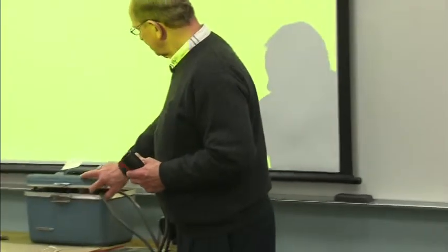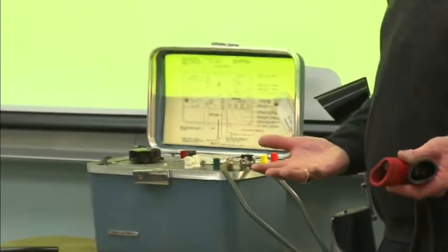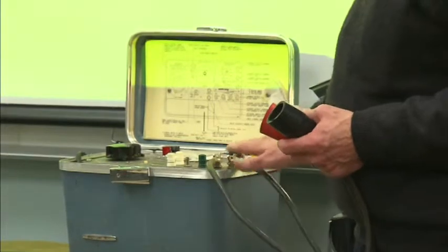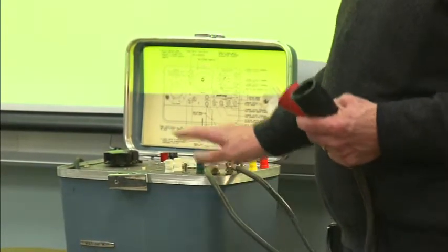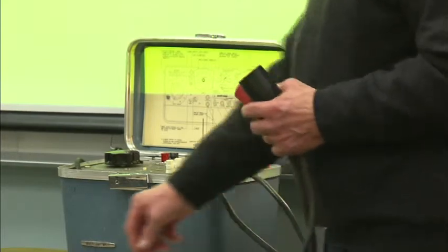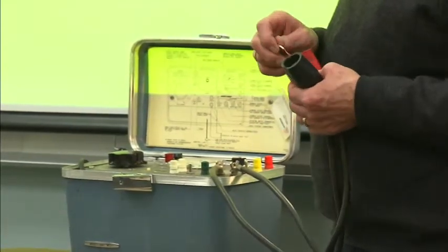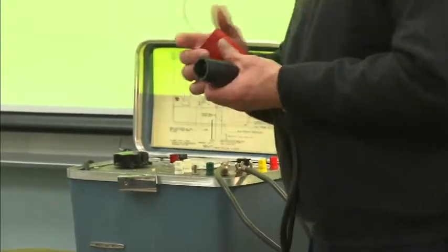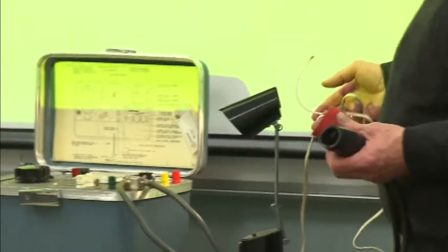And all I've got here is a test current generator. It's primarily used to test circuit breakers, fuses, that sort of thing. This can generate about 300 amps at low voltage. It's not the voltage that we're going to see the results of. What we're going to see is what the current will do to a small piece of conductor. Now this conductor is the same conductor that's feeding this light that's on right there.